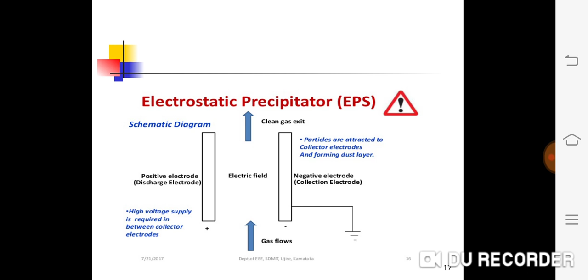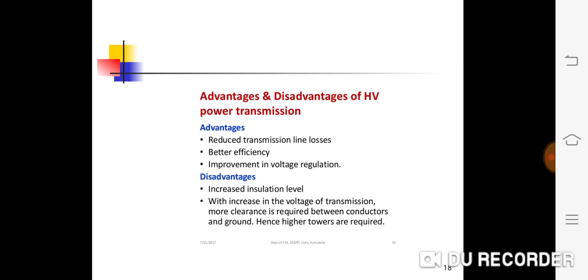Then, advantages and disadvantages of power transmission. High voltage transmission reduces the losses, improves the efficiency, and also improves the voltage regulation. What are the disadvantages? Increased insulation level. With an increase in the voltage of transmission, more clearance is required between conductors and ground. Hence, higher towers are required.